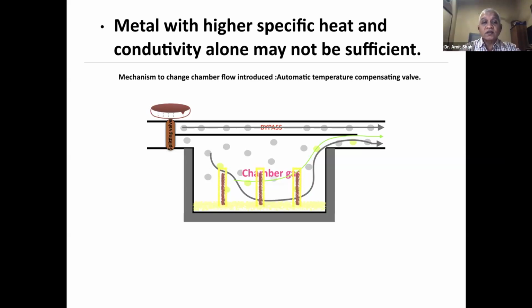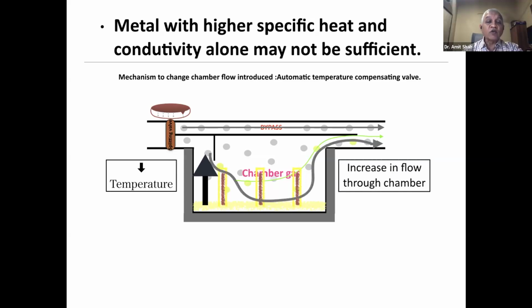Now, only putting in the metal may not be helpful. So what they have done was to add an automatic temperature compensating valve. Okay. A metal with higher specific conductivity may not alone be sufficient. So they've decided that we can adjust the flow. If the temperature of the liquid is dropping, the vapor pressure will drop. So we have to change the flow which is passing through the chamber versus bypass. To do that, they add what is called a temperature compensating valve inside the vaporizer. So when the temperature drops, it allows more gas to pass through the chamber.